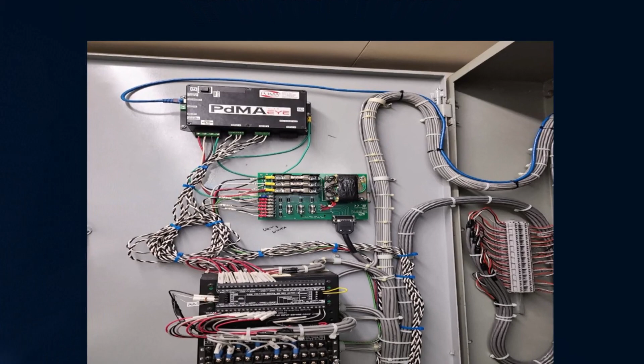So this is how they installed it. You can see here they're using 9 channels, tapping the voltage from the M-tap into the PdMA EYE, with additional current probes for the startup and running current of that motor. This is a good image showing the real estate comparison between the PdMA EYE and the M-tap 2 - shared voltage and independent current inputs from CTs.